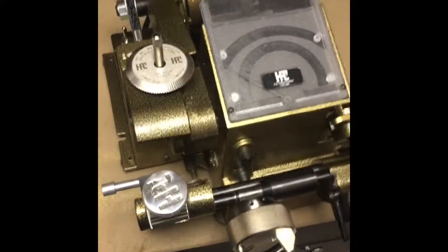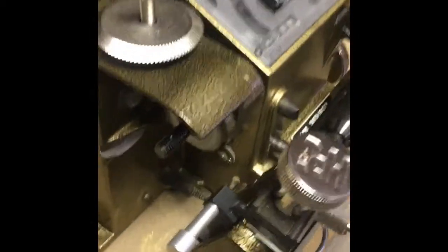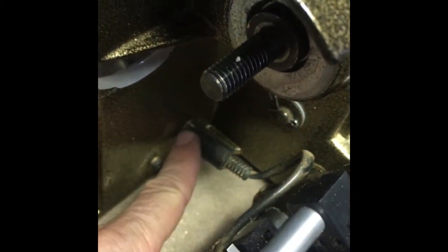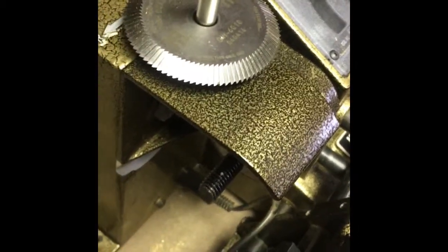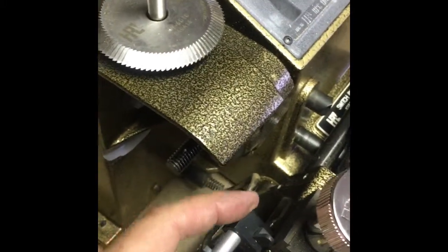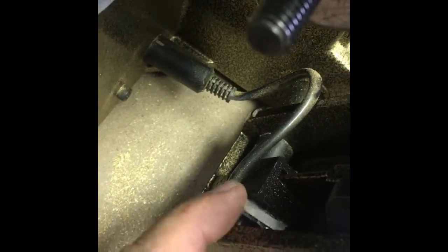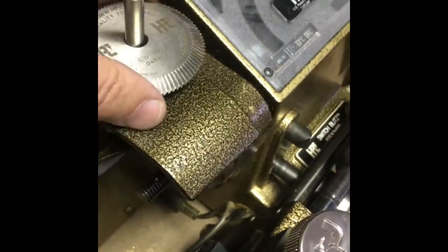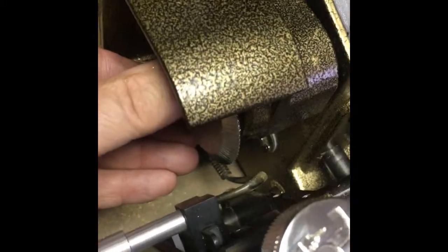Here's another issue that also happens with this machine that customers complain about and don't realize it's them or their lack of knowledge. So right here is a plug that a wire runs into this little sensor so that if this is down, the machine will start. If it's up, it will not. And that's to prevent you from actually cutting this. But there's shavings that get inside of here and hinder the switch. And when that happens, you'll get just a brief motion by the cutter. It'll look kind of like this. Just a quick back and forth, and that's it. And they'll complain the cutter turns briefly and then the machine does nothing. That means that this switch is either defective or more likely it's covered with shavings. So you just take a can of air, spray it in there real well, maybe lift up the machine, make sure that all the shavings are out, and you'll be good.